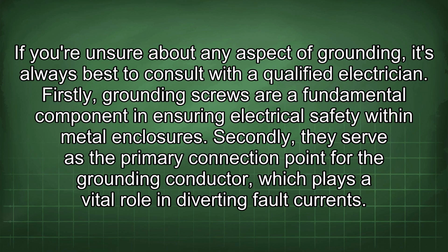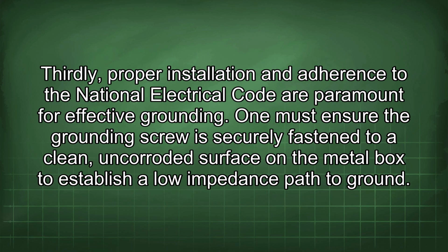Firstly, grounding screws are a fundamental component in ensuring electrical safety within metal enclosures. Secondly, they serve as the primary connection point for the grounding conductor, which plays a vital role in diverting fault currents. Thirdly, proper installation and adherence to the National Electrical Code are paramount for effective grounding. One must ensure the grounding screw is securely fastened to a clean, uncorroded surface on the metal box to establish a low impedance path to ground.